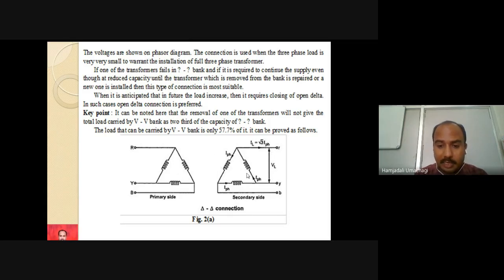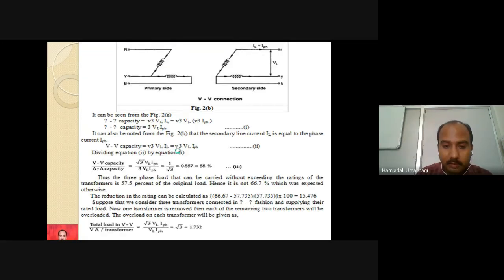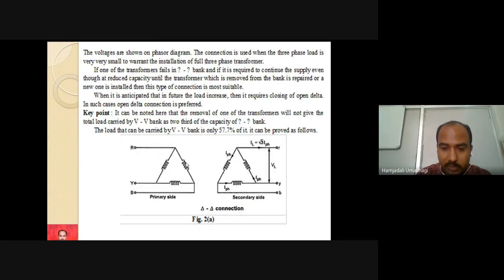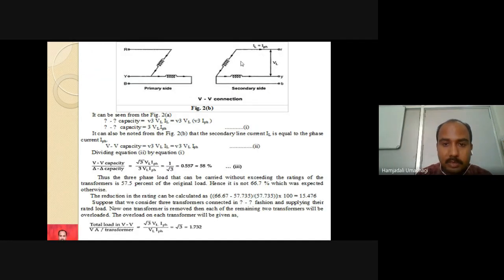So this is the circuit diagram for delta connection. Primary side RYB, secondary side RYB, and both sides are connected in delta fashion. This is figure 2A, the delta connection. Now, if one of the transformers is out of service, here if I say this transformer is out of service, and similarly on the secondary side this will be out of service, then it becomes open delta. Open delta means this will be absent, this will be absent. Now the connection will look like this. So this side winding is absent, and the connection becomes open delta on both primary and secondary side.